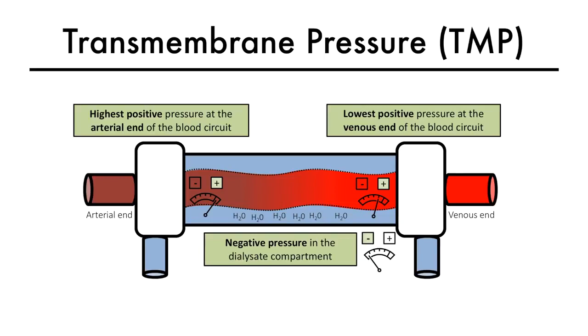The leakiness of the membrane to water depends on the size of the pores within the semipermeable membrane. The leakier the membrane, the higher its KUF or coefficient of ultrafiltration, and the lower the TMP required to attain a certain level of ultrafiltration.